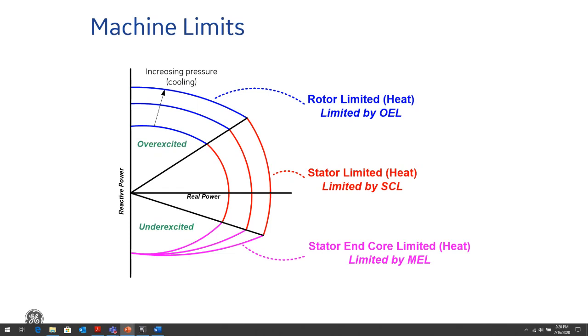Underexcited conditions can occur if we lose the field. If we lose control of the field, we can be in that underexcited limit. And there is certain protection that we call loss of field protection that we'll talk about to deal with those conditions. When we are in the overexcited part of the curve, a situation that can cause us to go into that overexcitation limit of the generator is again control failure. We're not able to control the generator properly and it starts to get overexcited. Another is operational error during offline manual regulation operation. Another is loss of the sensing voltage to our automatic voltage regulator. So the system is not reading the correct voltage, and it might go to an overexcited condition because it thinks it needs to supply more VARs.